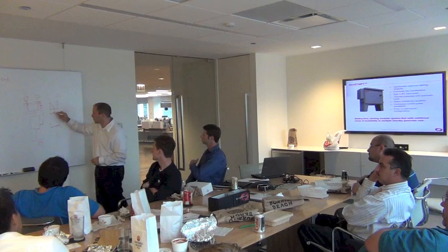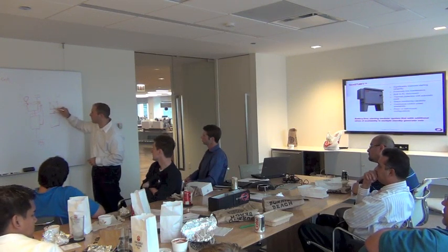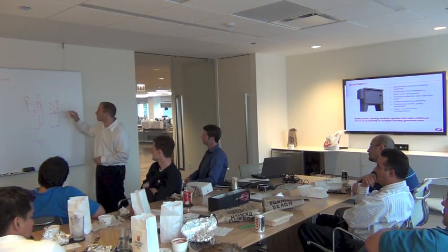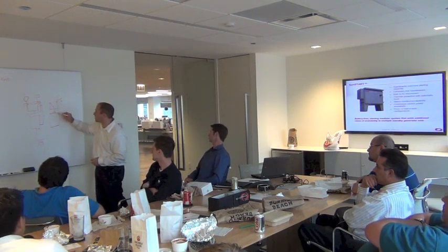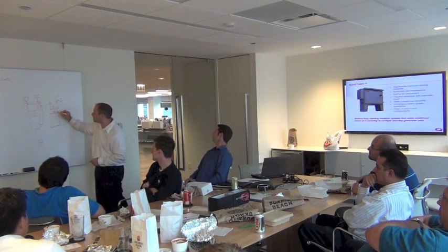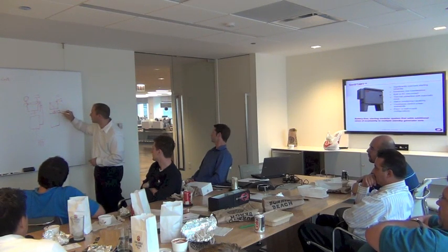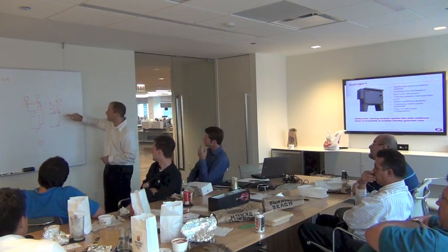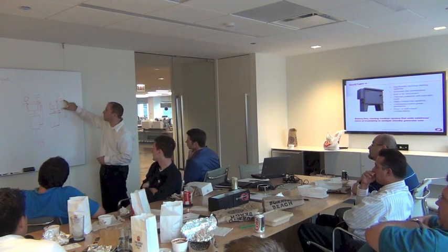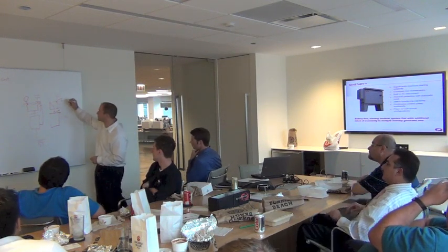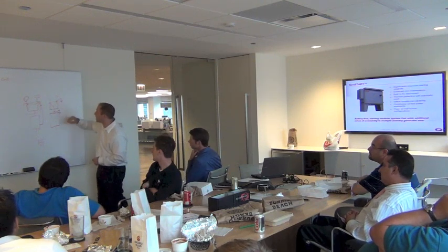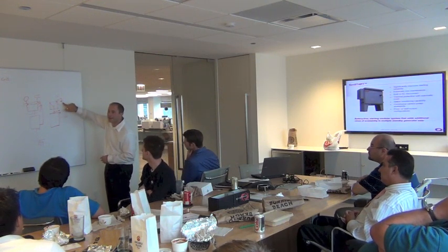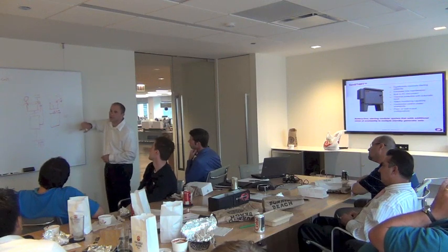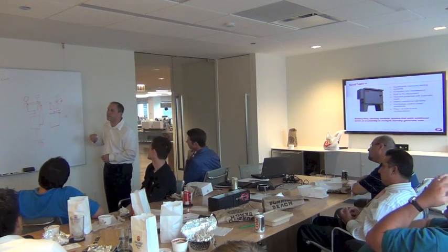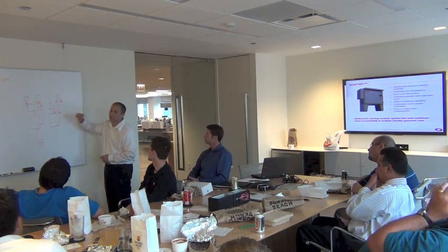And obviously, we always want to coordinate an outage by the same parameters as our transfer switch. So if this is set at +10, -10, we would always want this usually to be consistent or a little bit wider. This guy always needs to be equal to or tighter. In other words, if this was at -20, that could be a bad situation. You could have a -15% low line condition. This guy doesn't see the outage and this guy's into discharge. So it's always important to define an outage by the same parameters, under as well as over, and with frequency as well.